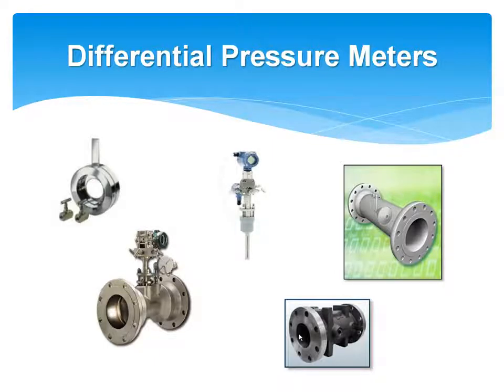Another very common class of meters that's used in steam measurement is differential pressure style meters. And as you can see here, there are many different types, from orifice plates and venturis to insertion style to different types of obstructions. There's a little subset maybe of these types of meters, which are variable area meters, where you're actually varying the ID of the meter based on flow rate. Those can be sensed with differential pressure or even strain gauge measurement. But again, there are many different types of differential pressure meters out there that are very commonly used.